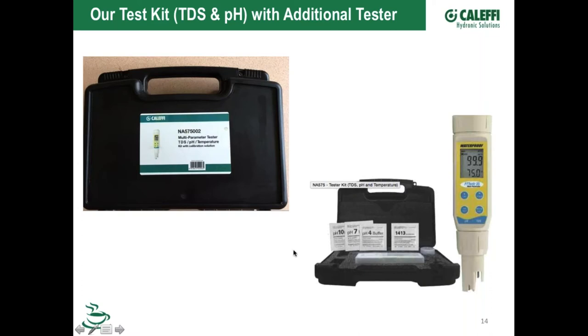So included in this kit are some samples that you use to adjust the pH and make sure it's reading correctly. Typically you do that at three different ranges, at 7, 10, and at a low range, so you can see a 4, 7, and 10, fluid that's been adjusted to that pH. So then you stick your meter in that and adjust your meter to read that. Same thing with the TDS, there's packages so you can recalibrate it. It's a pretty nice meter that has everything in there to recalibrate it.